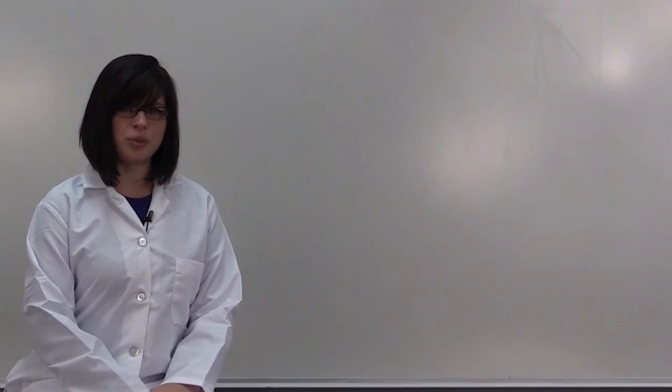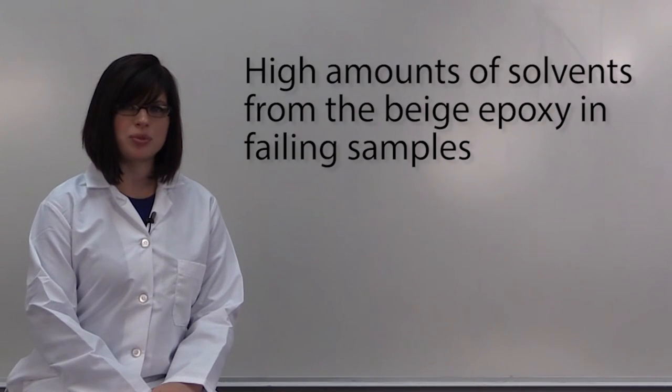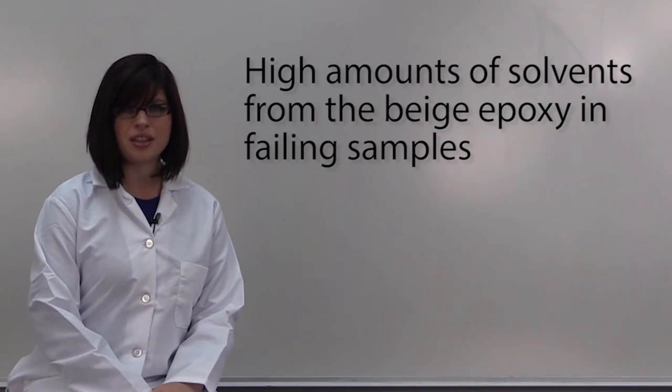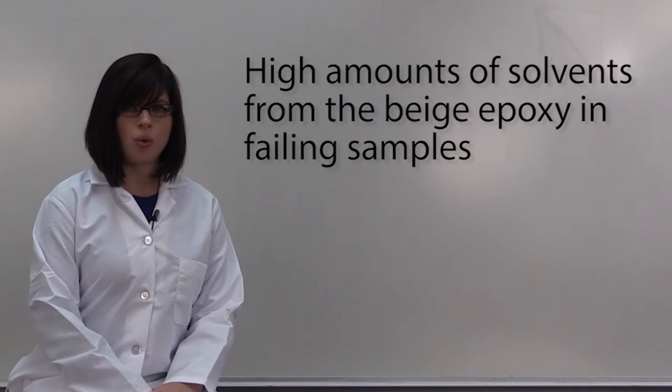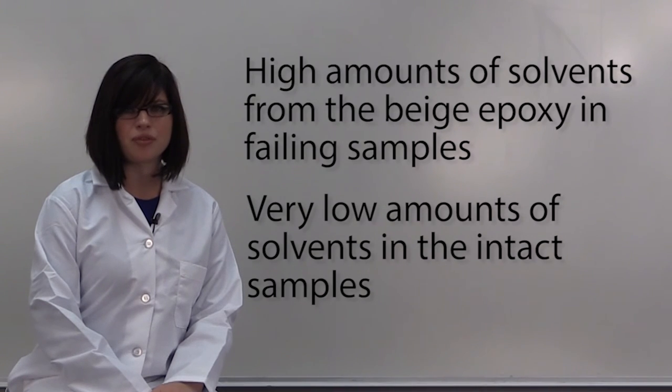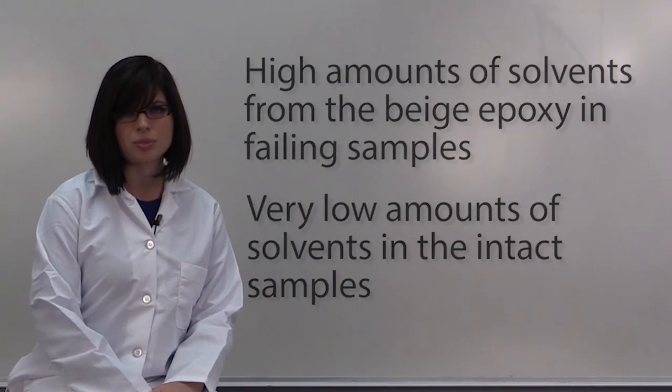The analysis revealed the presence of solvents in the failing samples. The solvents that were consistent with the solvents listed in the Safety Data Sheet, SDS, of the beige epoxy coats. The quantity of solvent materials was higher in areas where blistering occurred as opposed to samples taken from areas that did not experience blistering.